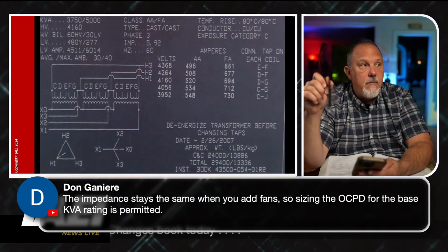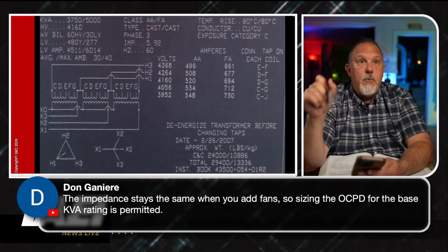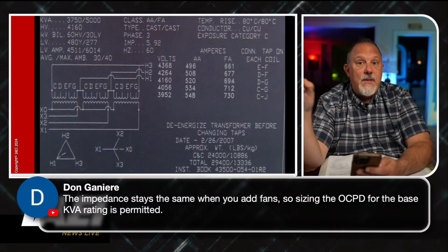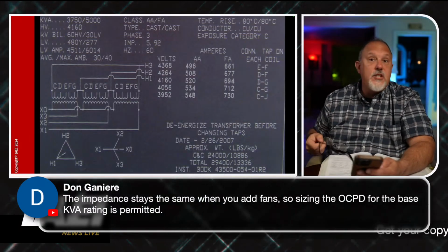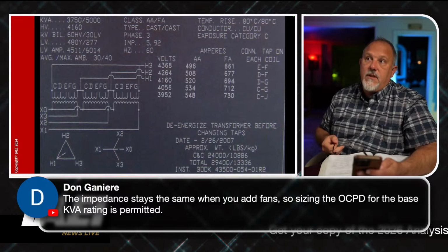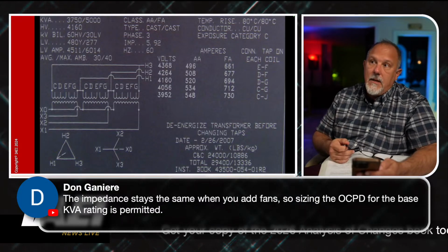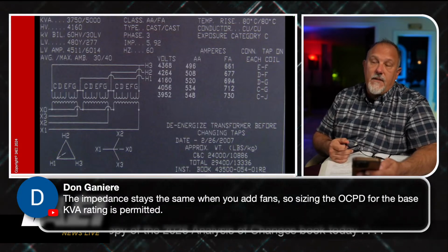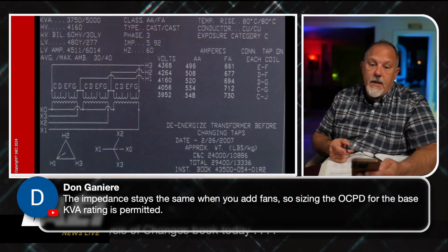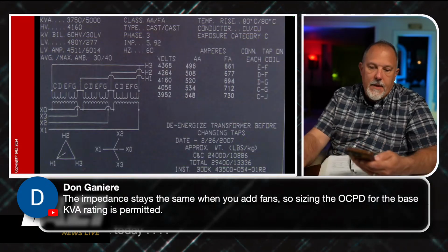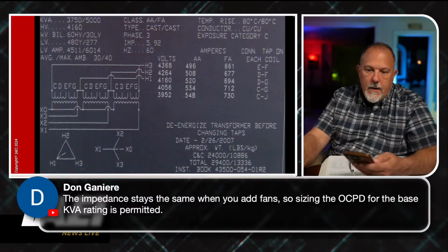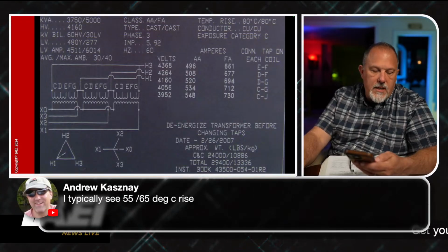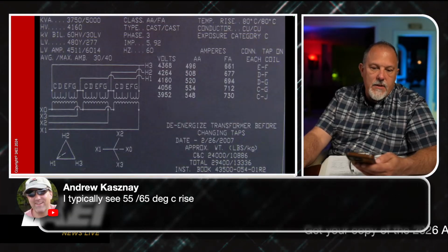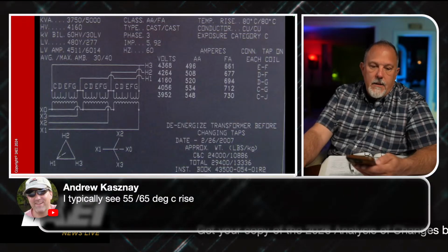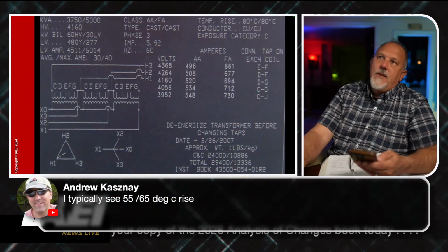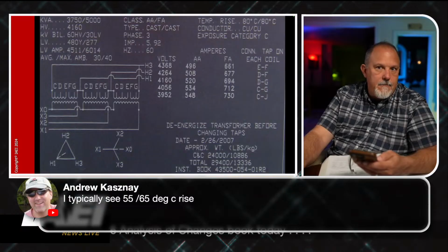So I think the significant, important decision that needs to be made is on the secondary. I don't have any prohibition that I can't use the 5,000. I guess there would be, if it's a future fan added, because I don't have fans. It's my overload protection I'd have to think about. Andrew says he typically sees 55, 65 degrees C rise. Yeah, but your insulation of the conductor is 90 degrees C.